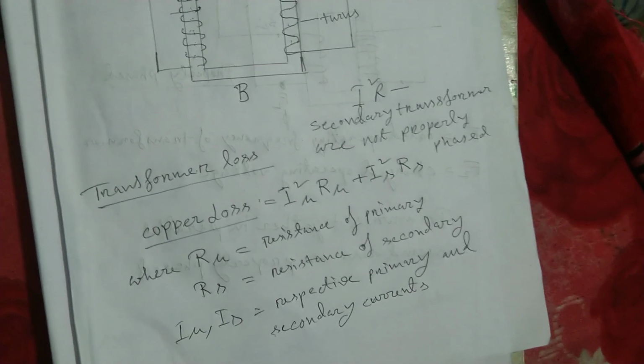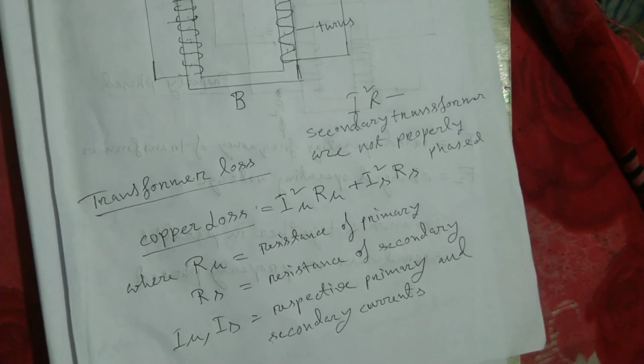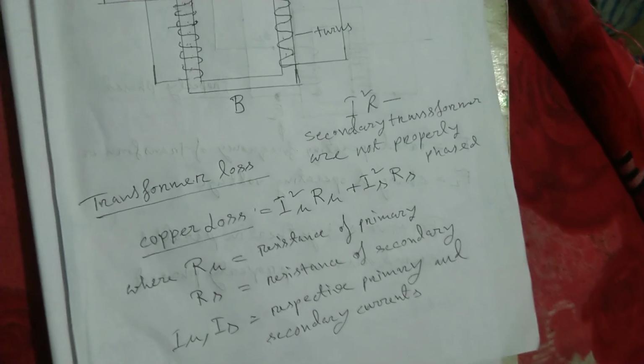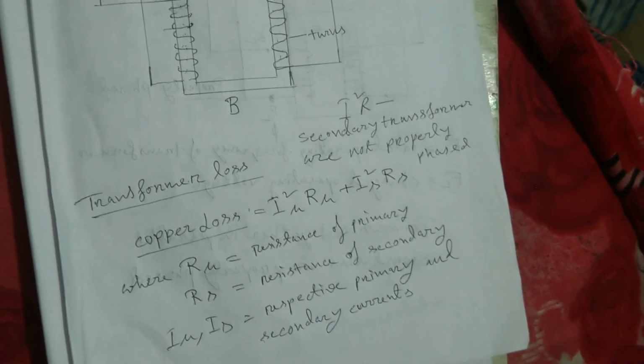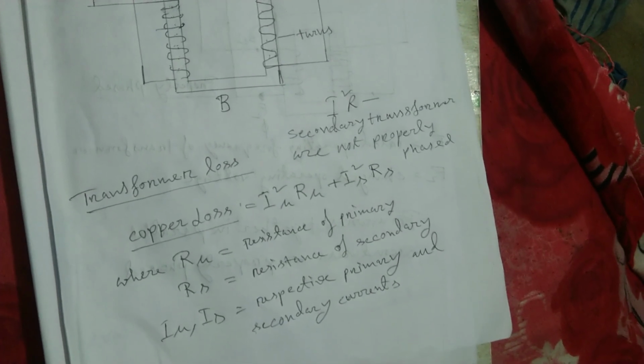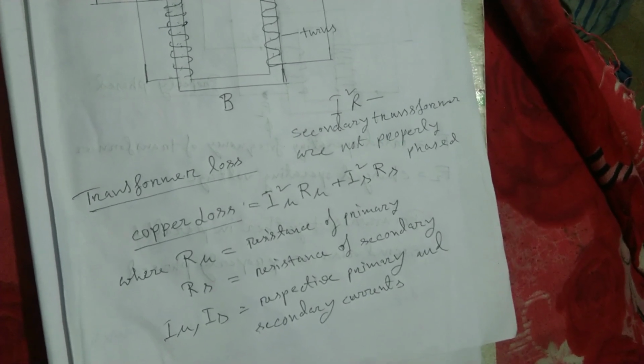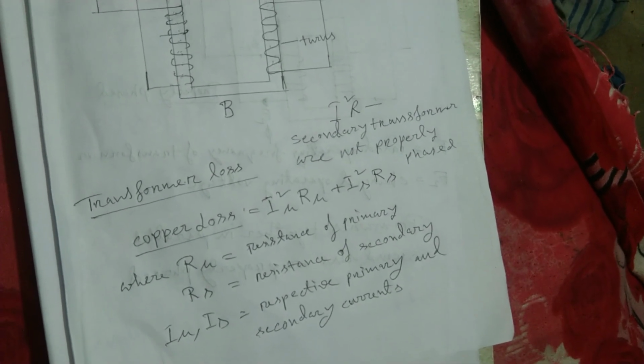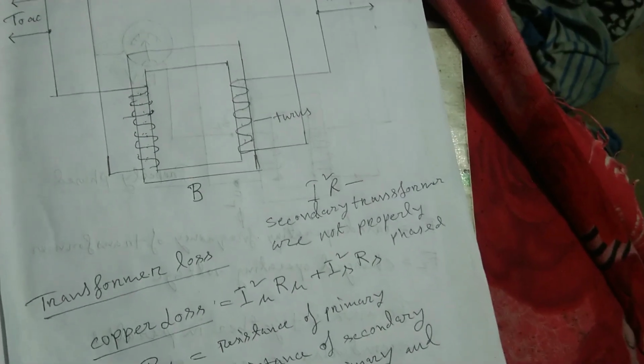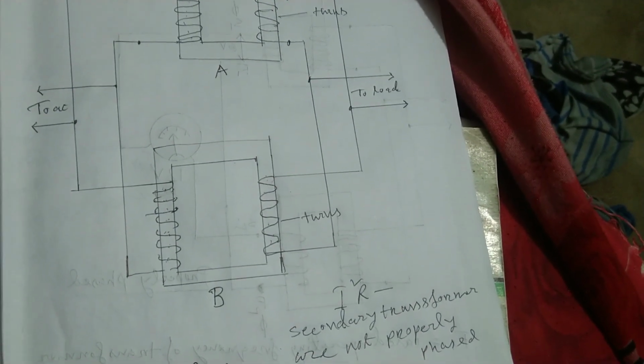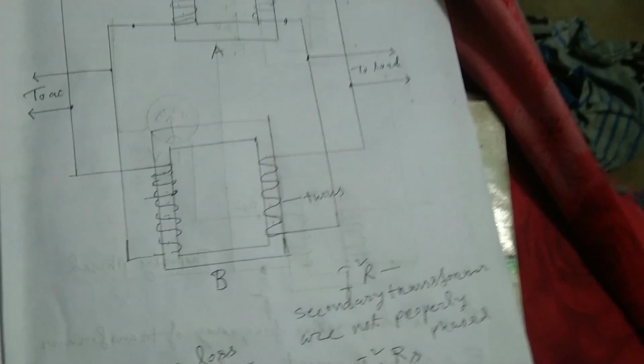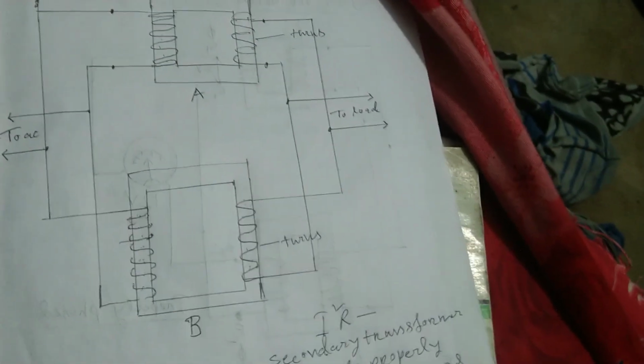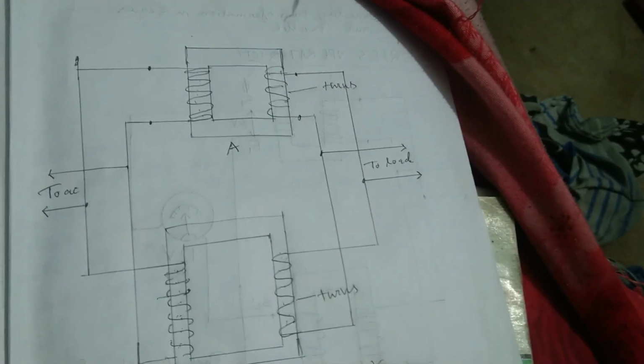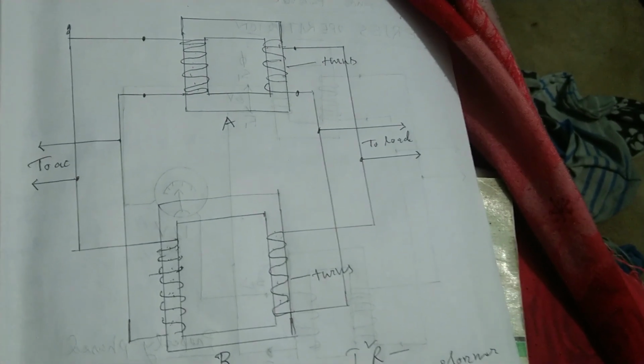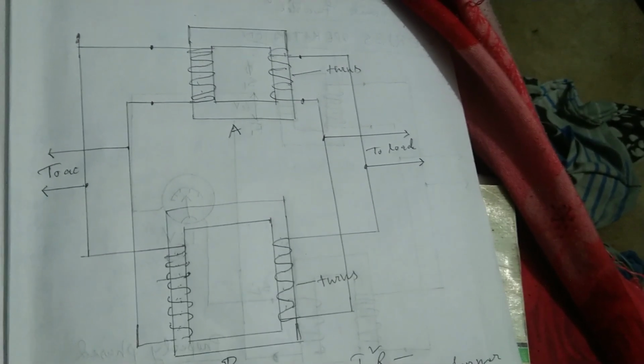then on parallel operation, the result is a short circuit that burns out the winding. Even if two transformers of the same make have the same number or letter terminals, it should not be assumed that they will be properly phased for parallel operation. For two transformers in parallel operation, we connect the primaries in parallel and the secondaries in parallel.